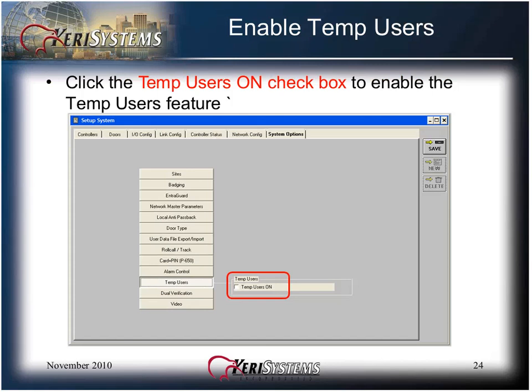Click the Temp Users On checkbox to enable the temp users feature. The temp users feature allows you to assign cards that are active and valid for finite periods of time and then automatically expire. It is particularly useful in applications where memberships or temporary workers are present. Credentials can be programmed to activate sometime in the future and then automatically expire at the end of a designated time period. Temp users only works on PXL 500 series controllers and is only available in DOORS32 software versions 4.10 or higher. Temporary cards is described in detail in the advanced DOORS presentation.